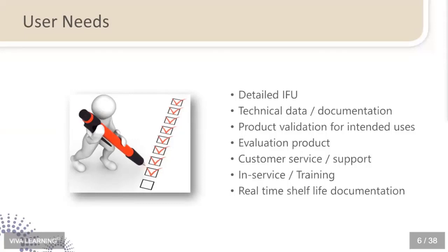So what are the details that we need as users? What do we need to have available within our sterility assurance program and documentation? We need to have the detailed IFUs, instructions for use, that include the reprocessing instructions for each and every item, each and every instrument that we have within our portfolio of instruments. So you can't just say, because I'm using this brand of instruments, I only need to have one. It is going to be different if you have a forceps or you have a scaler. So you have to have those detailed IFUs available. Likewise, you have to have the detailed IFUs for any of the sterilization packaging because it has been validated for use, and you have to make sure that you're following each of those steps. Some information that may not come automatically with product are technical bulletins or technical data, but you can get that information from the manufacturers of sterilization packaging.